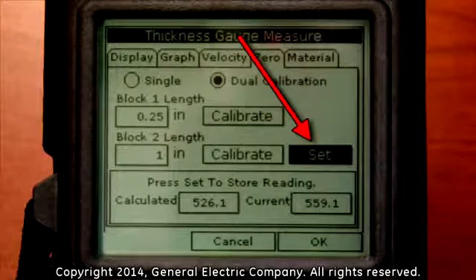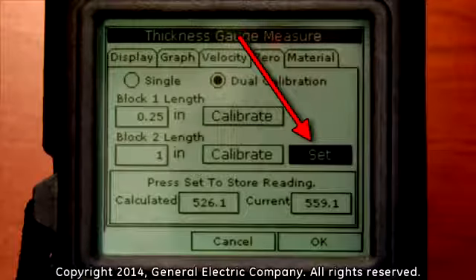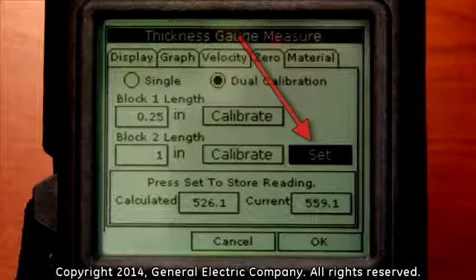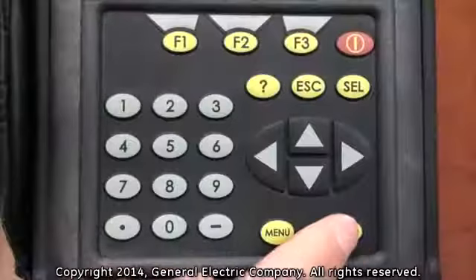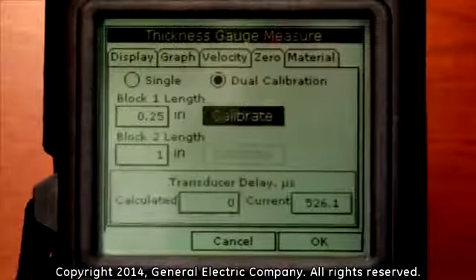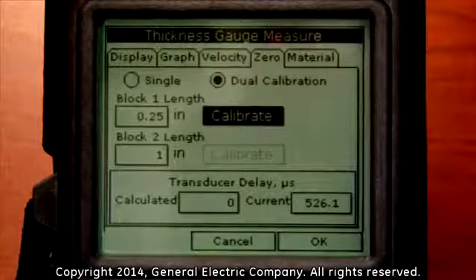When the calibration process for the block 2 length is accepted, you will see that there is a new selection highlighted called Set. With the Set function highlighted, press the Enter button on the keypad. This will finalize the calibration of the thickness gauge.